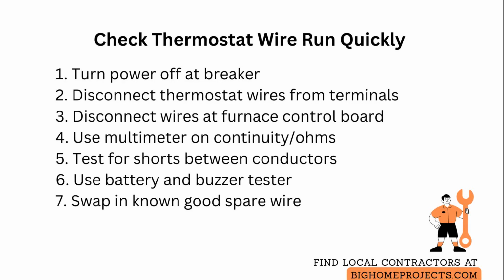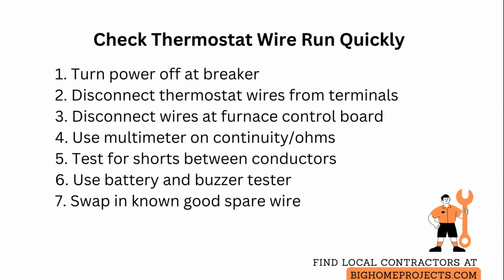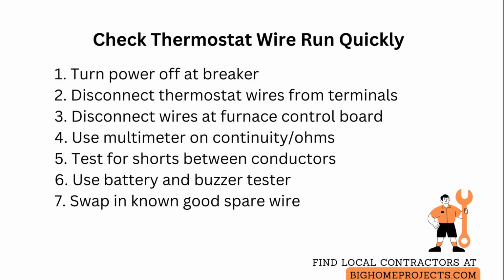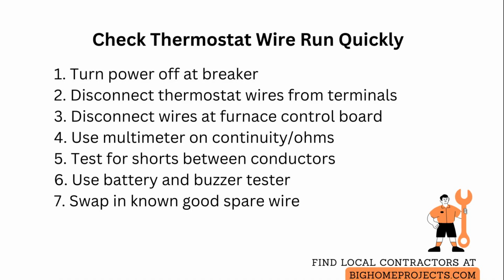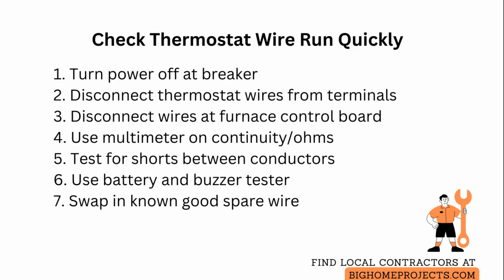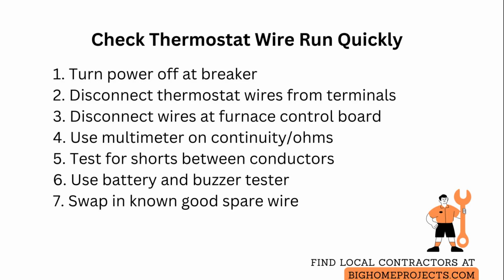If you do not have a multimeter, use a battery and a small light or buzzer to create a simple continuity tester, connecting the tester across the wire pair to see if the circuit completes. If continuity fails, swap in a known good spare thermostat wire or temporarily run a single conductor jumper to confirm the system responds before replacing the permanent cable.